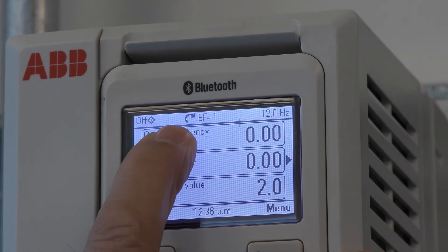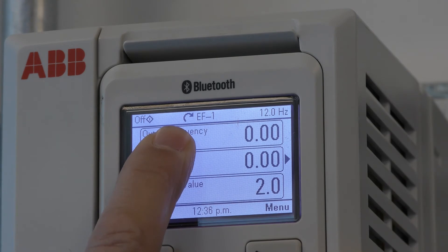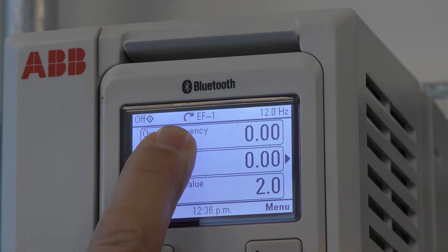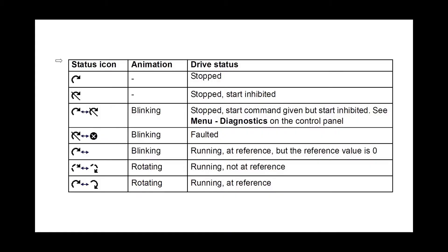Now I'd like to point out the status icon, which is a curved arrow. That tells you the status of the drive, the motor, and the direction of the reference frequency. When the curved arrow is sitting still and not blinking, it means the drive is stopped with no start signal. If there's a line through the curved arrow and it's not moving or blinking, it means the drive is stopped due to a start inhibit. When it's blinking between the curved arrow and the curved arrow with a line through it, it means the drive is stopped, the start command is given, but it is start inhibited.